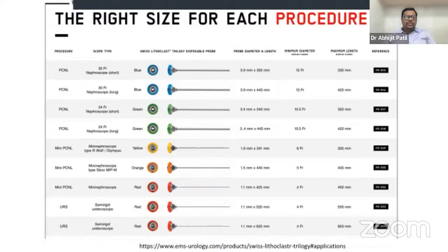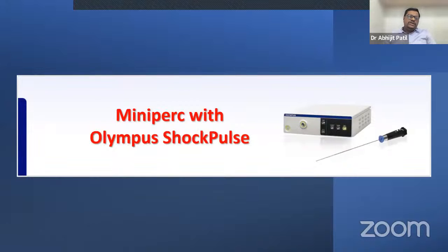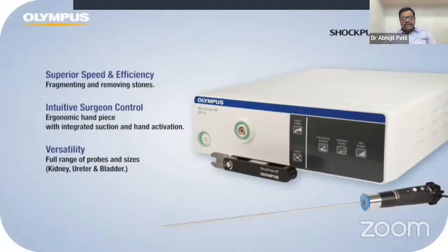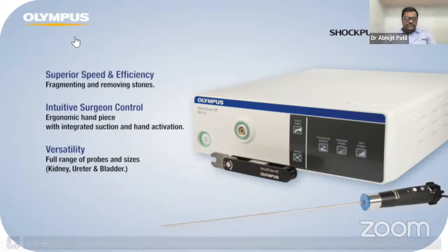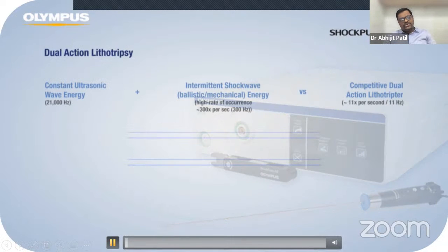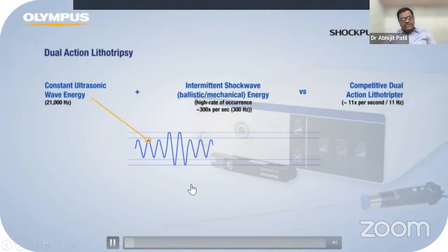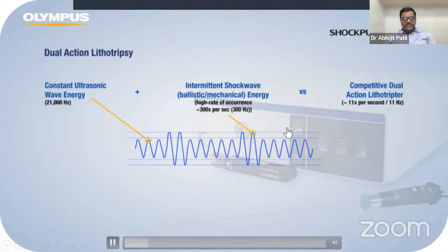So there are various probes for Trilogy. The conventional probe that we use for standard PCNL is 3.4 mm, and for mini PCNL it is 1.9 mm. Coming on to the next technology, which is mini PCNL with the Olympus Shock Pulse. Now, what the Shock Pulse has is that it also has the same three components. These are the components of Shock Pulse. It has a baseline ultrasonic energy, and in between, the intermittent ballistic energy is given.